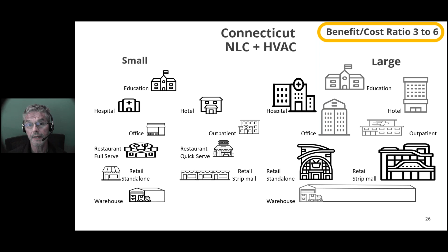If we add demand response, we pick up a few more building types: small warehouses plus large office and outpatient. By integrating NLC with HVAC controls, all of the remaining large building types are added. Using the utility cost test to evaluate NLC HVAC integration in Connecticut, the benefit-cost ratio in most building types varies between 3 and 6, a delightful range where the value of benefits is significantly larger than the cost.